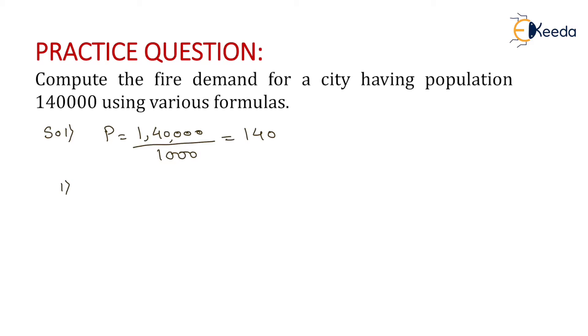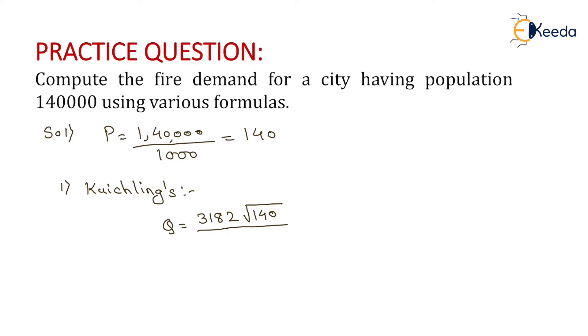The first formula will be the Kuichling's formula. According to Kuichling's formula, the amount of water required for fire extinguishing purpose equals 3182 root P. The value of P is 140, and we want the answer in meter cube per second, so we divide by 60,000. We get the answer as 0.627 meter cube per second.